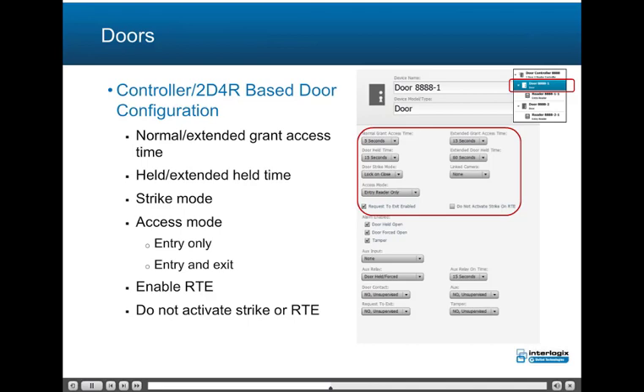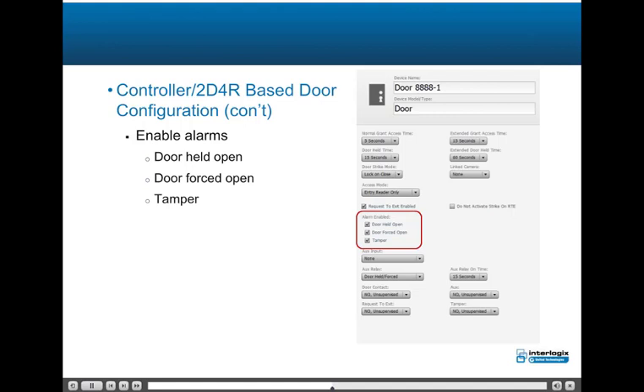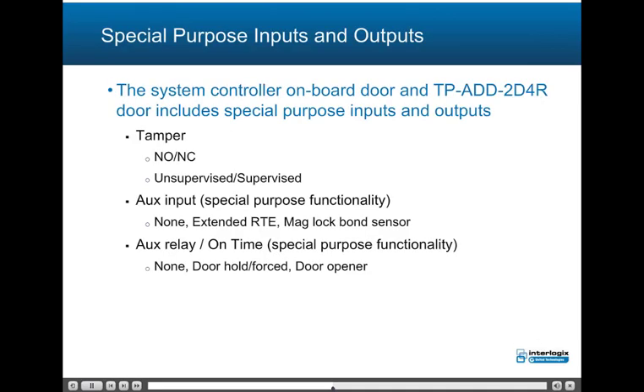The Controller/2D4R based door configuration includes configuration of normal/extended grant access time, held/extended held time, strike mode of lock on close or timed unlock, access mode of entry only reader or entry and exit readers, and the ability to enable request to exit and do not activate strike or request to exit. Alarms that can be enabled include door held open, door forced open, and tamper. Special purpose inputs and outputs include Tamper (configurable for NO or NC, unsupervised/supervised), Aux input for none/disabled, extended request to exit, or magnetic lock bond sensor input, and Aux relay/on time for none/disabled, door hold and forced, or door opener for motorized door openers.